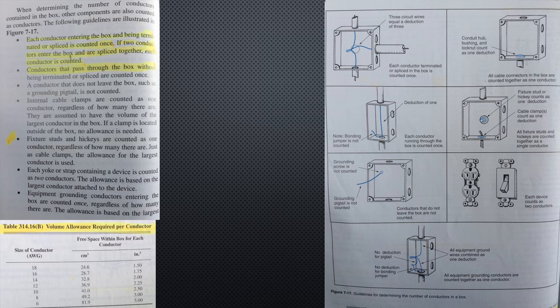Fixture studs and hickeys are counted as one conductor, regardless of how many there are. Just as cable clamps, the allowance for the largest conductor is used.